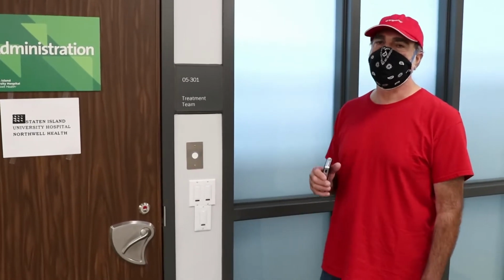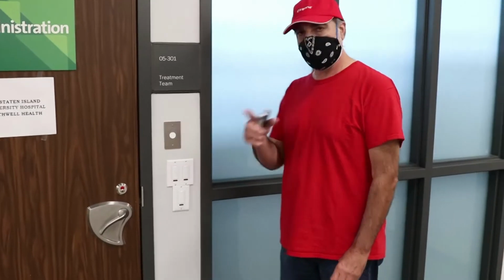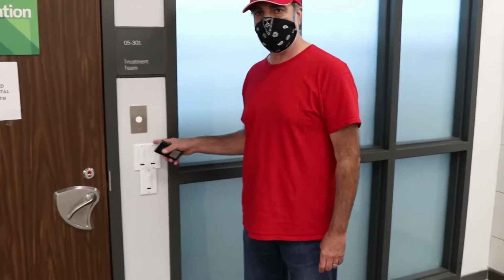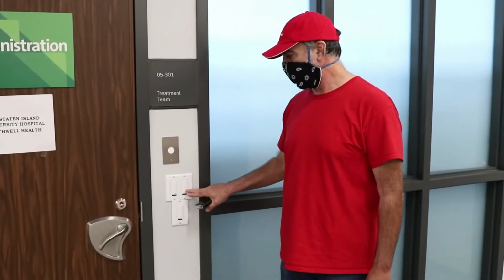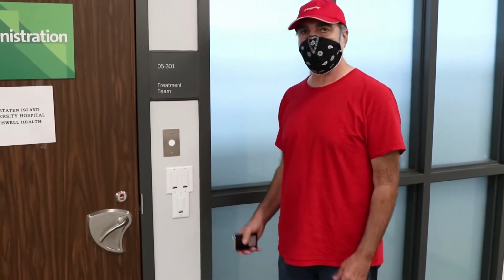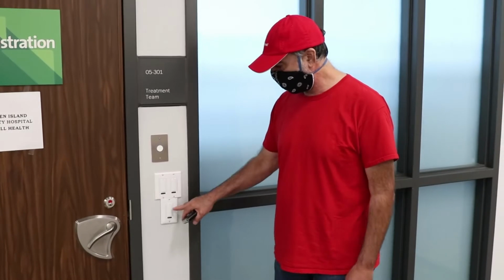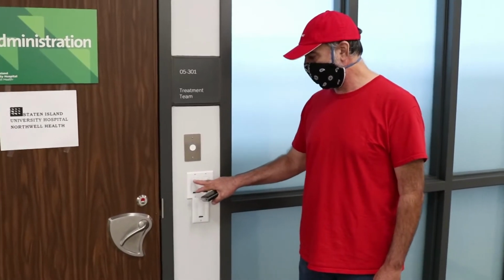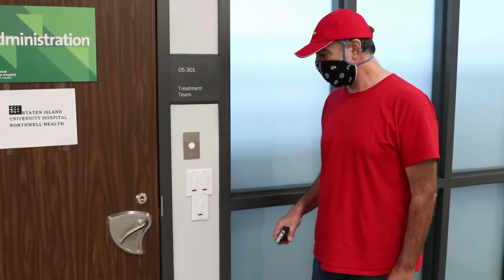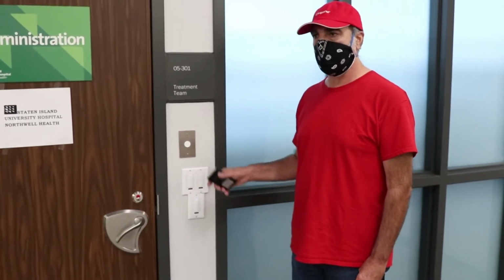The way the lights are scheduled in the building, at 7 a.m. the lights turn on, and the switches throughout the public areas, that would include the ones in the lobby, corridors, are locked out. So they actually don't turn the lights off, even though the little indicator is still active, but the lights do not track what the switches do.